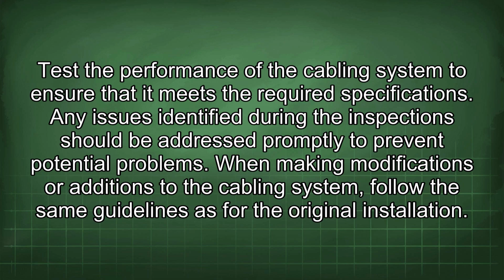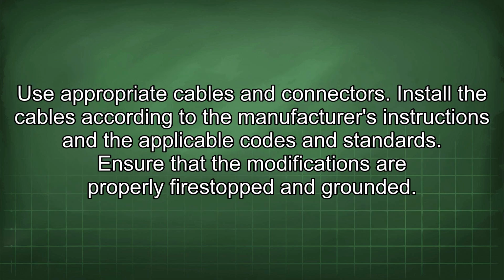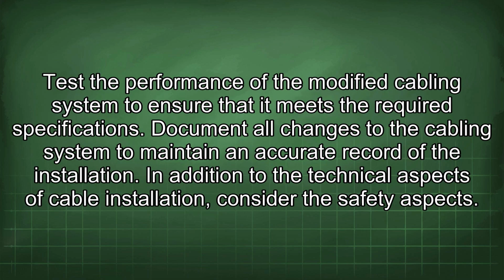When making modifications or additions to the cabling system, follow the same guidelines as for the original installation. Use appropriate cables and connectors. Install the cables according to the manufacturer's instructions and the applicable codes and standards. Ensure that the modifications are properly fire-stopped and grounded. Test the performance of the modified cabling system to ensure that it meets the required specifications. Document all changes to the cabling system to maintain an accurate record of the installation.